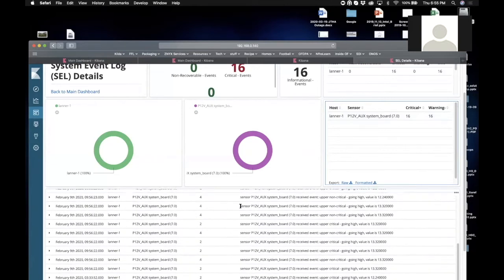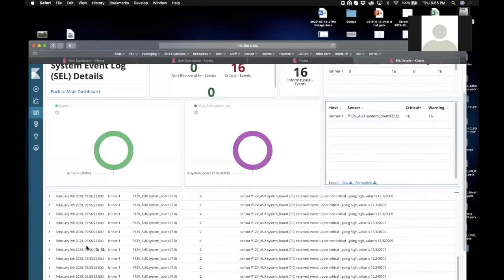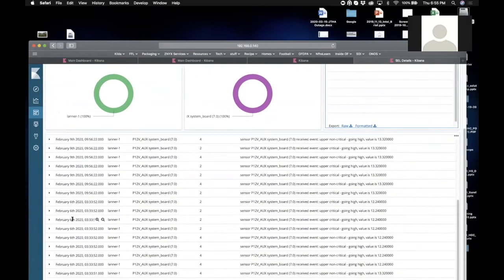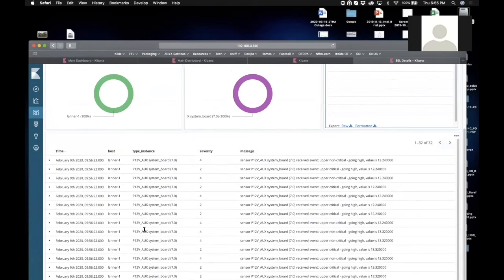So my guess is that these two events, they happen on separate dates. These two events may have been a power supply that you plug in and while the power is stabilizing you had a slight overvoltage situation that was maybe caused by a transient inrush current and it went away. So it lasted less than a second and it returned to normal, so don't really think this is an issue.